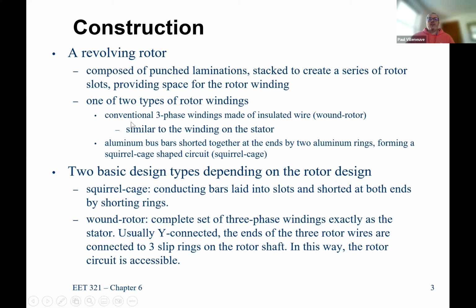You also can use the other design, which is the most common design, called a squirrel cage induction machine. This is the most common one because all you have is aluminum bars, and you might have some windings as well, but you basically have some aluminum with some windings, and those are all shorted together. So you still have that 3-phase set of windings, and you use that to get your 3-phase windings.